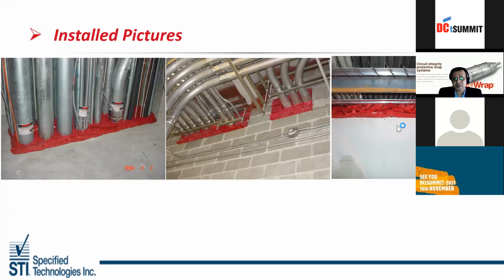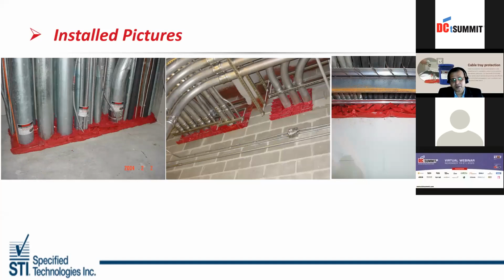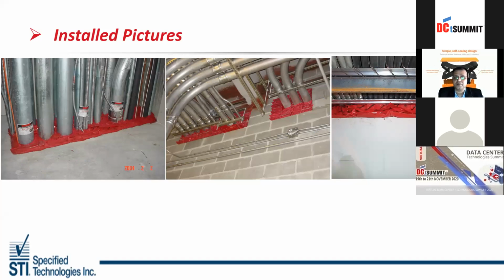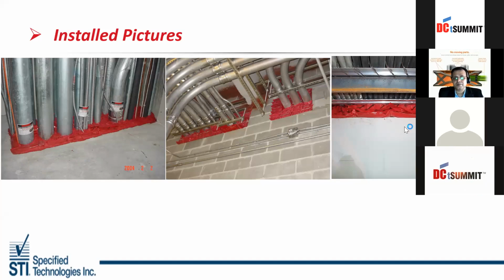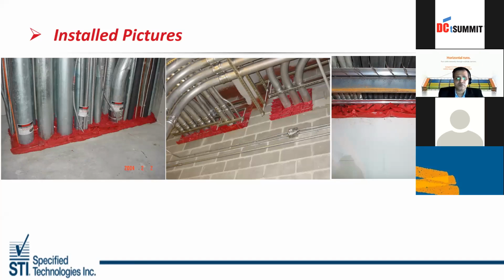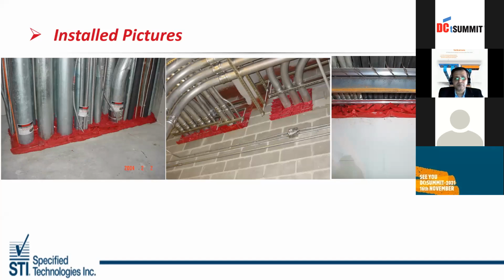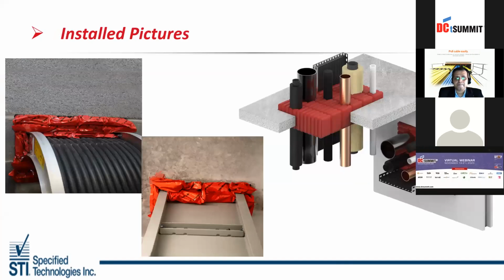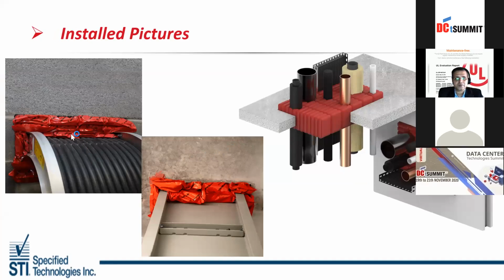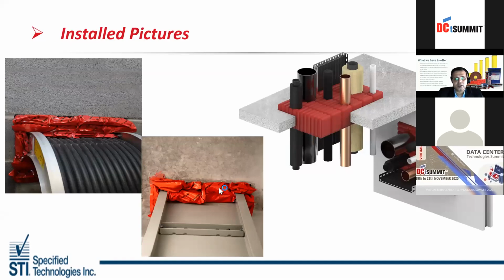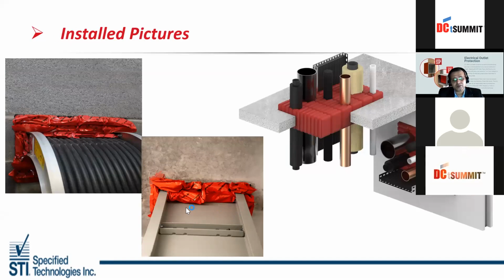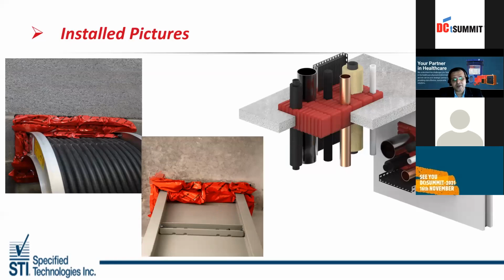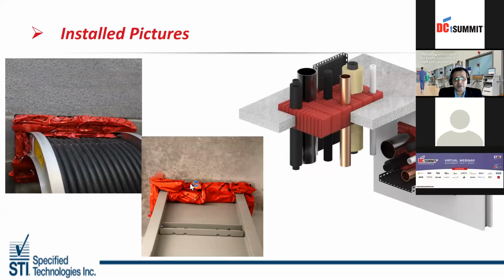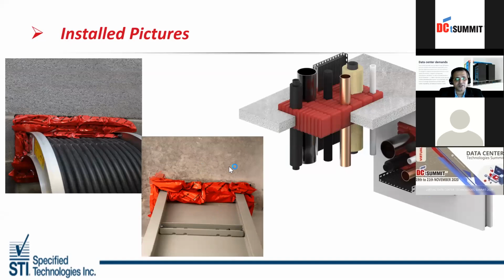So in all three different scenarios, where you have metallic pipe and cables, insulated pipes and metallic pipes, and cable trays, pillows can be used as per the site requirement, and if you feel there might be additions, you can use a pillow. Some more install pictures which I've tried to explain here. You can see the cables passing through the wall. Here it's an empty cable tray. This is an area where you feel that after 6 months or 1 year down the line, you will have cables passing through. Even if there are no cables, it will still be a fire stopping product in that scenario.